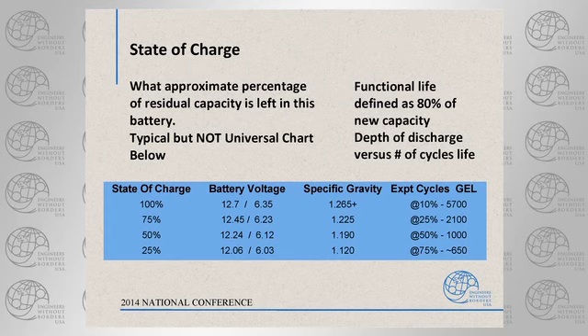Real quick. Go ahead. All right, low voltage disconnects. Remember I talked about a low voltage disconnect and a charge controller. If you don't have a charge controller, make sure you got a low voltage disconnect somewhere in your system. Something that says, that battery, you've used all I want you to use of that battery. I'm not going to let you drain it any lower than that percent load. Saving batteries everywhere from too deep a discharge. It's going to disconnect the load to save the battery.